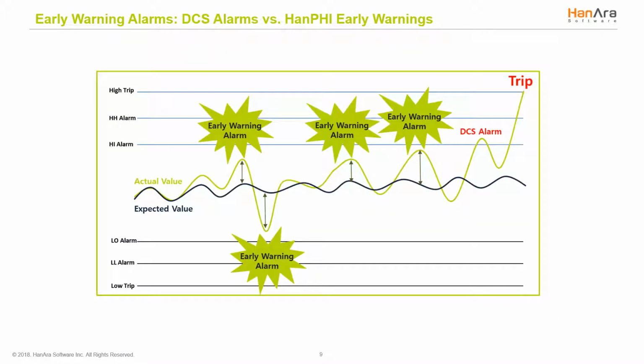What's important to note about HanPHI is that it provides early warnings regardless of what the DCS alarm level is set to. Existing alarms like the DCS generate an alarm when the value reaches a specified alarm set point, regardless of the external environment, load, or season. In contrast, HanPHI and our advanced pattern recognition considers all of this to provide early warnings. When a DCS alarm occurs, it may be too late to act as the breakdown is imminent, causing equipment damage and loss of money and time. In contrast, HanPHI provides added lead time to respond to exacerbating equipment conditions, transforming reactive maintenance to predictive maintenance.